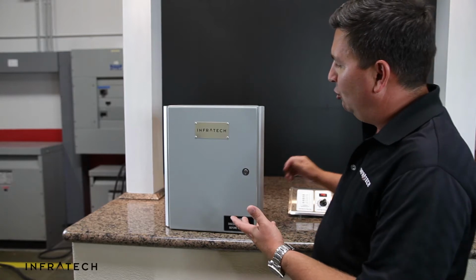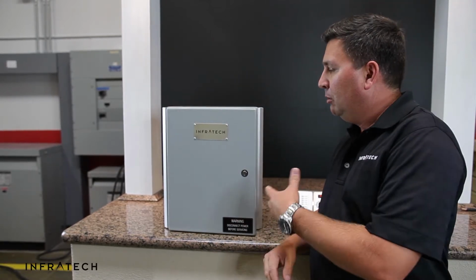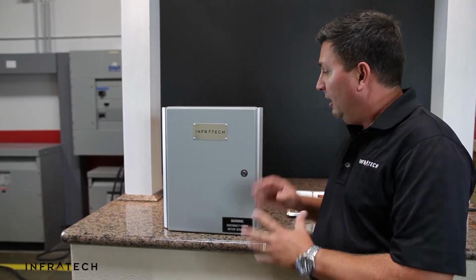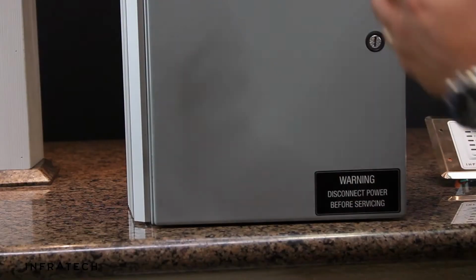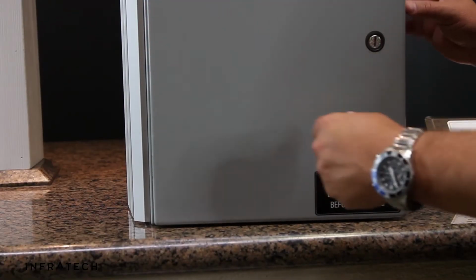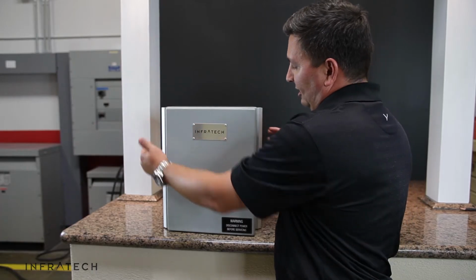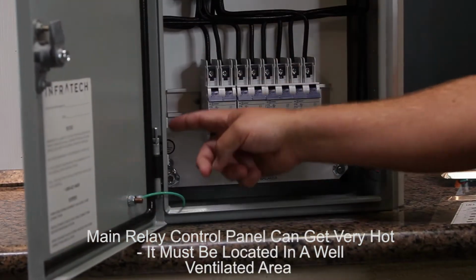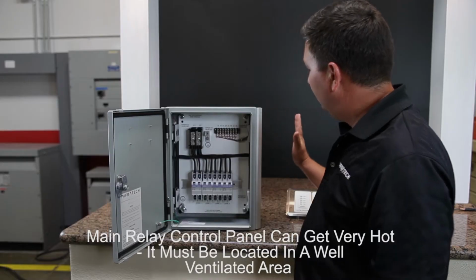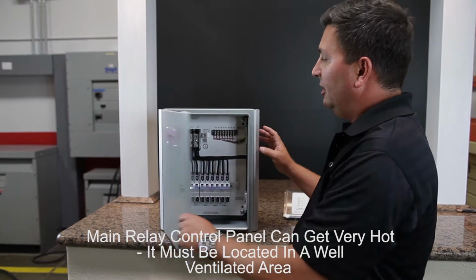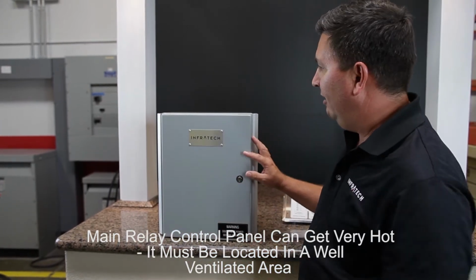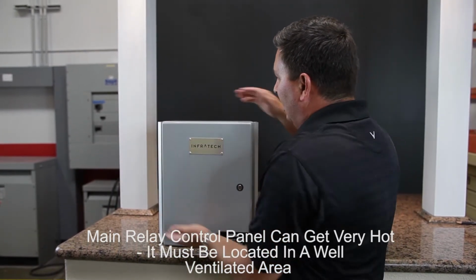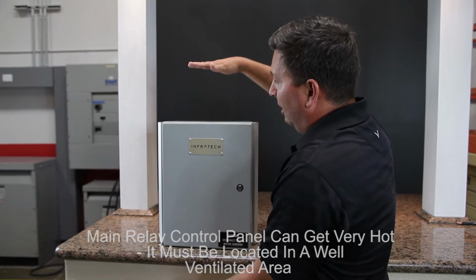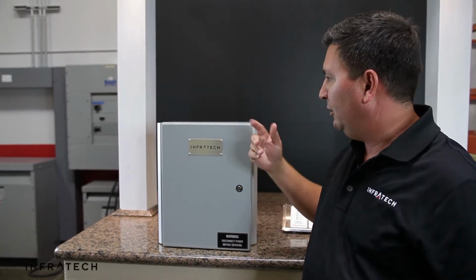The main relay control panel is NEMA 4 rated. It's suitable for indoor and outdoor use and is completely weatherproof. Our solid-state controls have external heat sinks. The solid-state relays inside operate very hot, and we need unrestricted ventilation to cool the relays. In a well-ventilated area, you'll need at least 6 inches to each side and 6 or 12 inches above and below to allow unrestricted airflow.